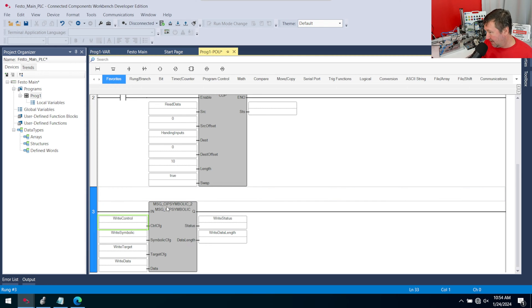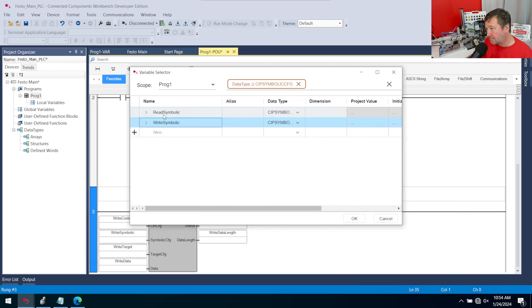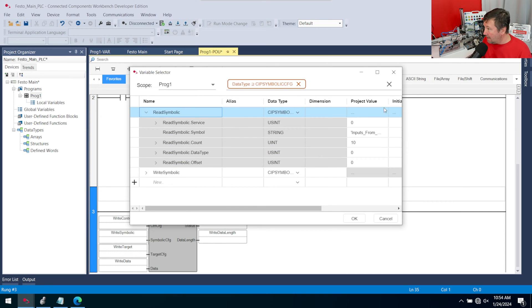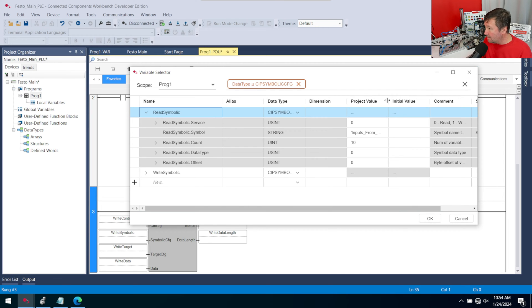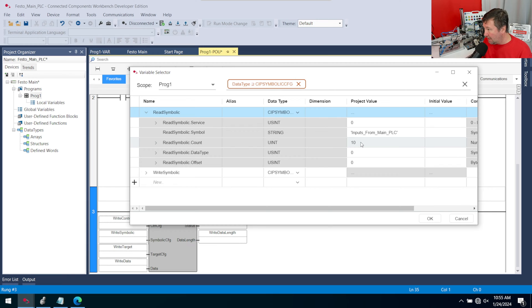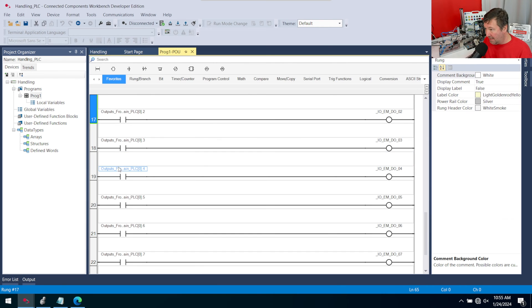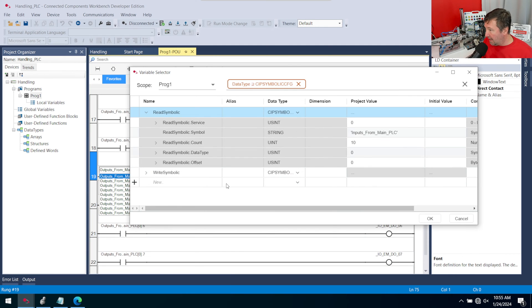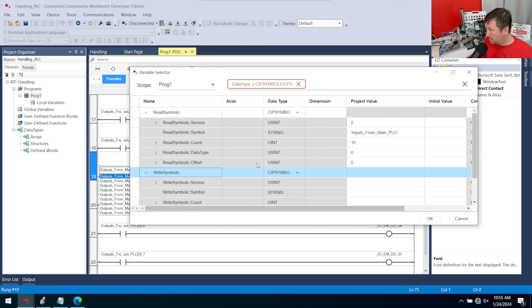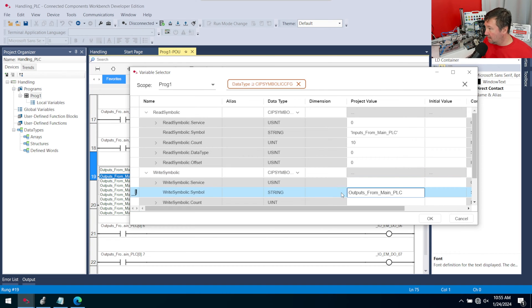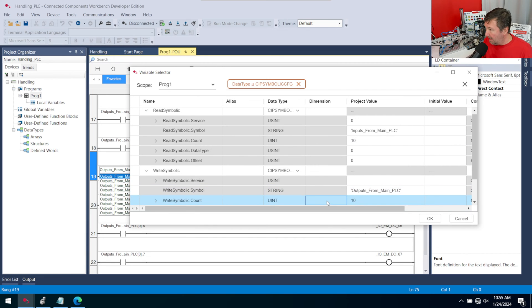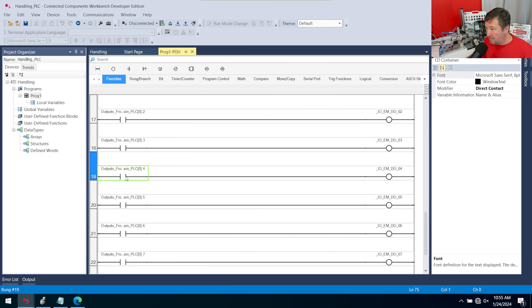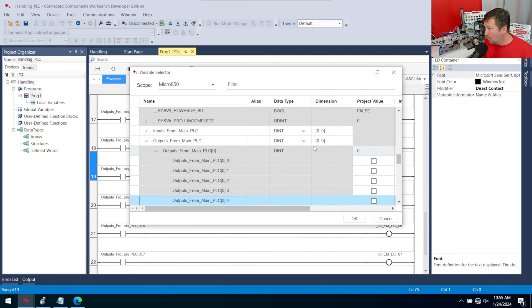I'll show you that you can actually hit the cancel button on this next one. Let's double-click on our write symbolic and open up the read for comparison. The key thing is the tag name in the other PLC and the length. In our other PLC, the tag name is going to be 'outputs from main PLC.' I'll highlight that, right-click, and copy it. Then open the write symbolic and paste it in. Our count is going to be 10, because over in that PLC we made this an array with a length of 10 — elements 0 through 9.